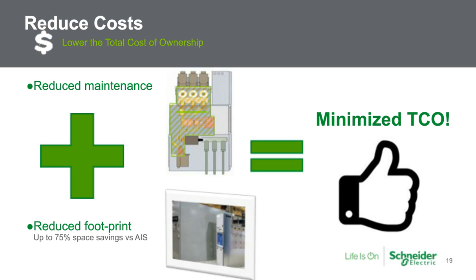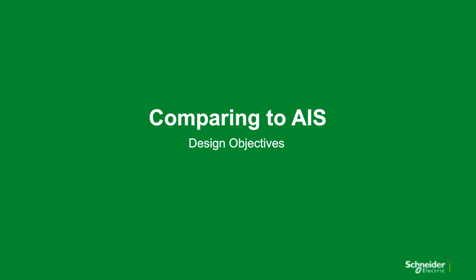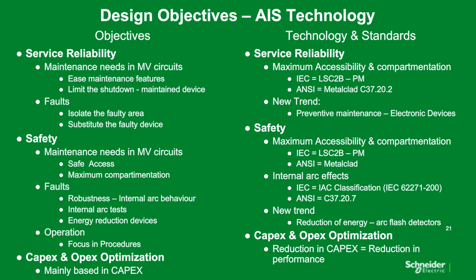So with that being said, how do we really compare to air-insulated switchgear? This is kind of the big talking point, mostly in the U.S. where gas-insulated switchgear is kind of in its infancy. The main points I want to address with the next couple of slides are the design objectives of the two types of switchgear. First, with air-insulated switchgear, I talked about this at the beginning, and I'll talk about it again, the objective is to make it easier to maintain the switchgear and make it as safe as possible to maintain or troubleshoot it. So the assumption is that you're going to have many failure possibilities in the bus bar compartment or with the circuit breaker. So the idea is to make it as easy and safe as possible to replace that failed component. This doesn't necessarily address the causes of a lot of these failures.